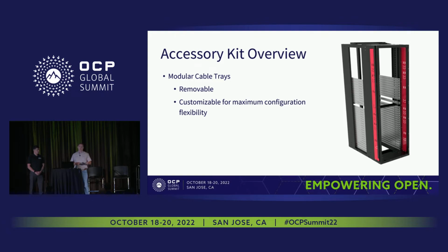In previous versions of the rack, for example in V2, those cable trays were actually welded into the frame, so you didn't have that same level of flexibility. You kind of got what you got, and you had to create a completely new SKU for the rack if you wanted to make changes in that area. The second thing this does for us is circularity and reuse, which is a big priority within Meta. As the first implementation of the rack comes to end of life, we can very easily change these out and reconfigure our racks and give them a second life.